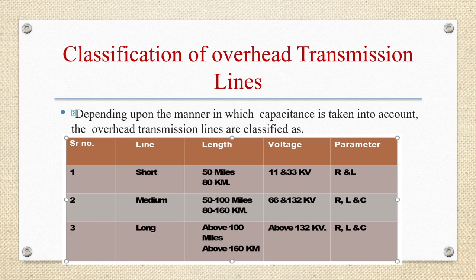It can be emphasized here that the exact solution of any transmission line must consider the fact that the constants of the line are not lumped but are distributed uniformly throughout the length of the line. Lumped means they are not coming together; they have to be distributed uniformly, that is, placed along the entire transmission line. However, reasonable accuracy can be obtained by considering these constants as lumped for short and medium transmission lines.